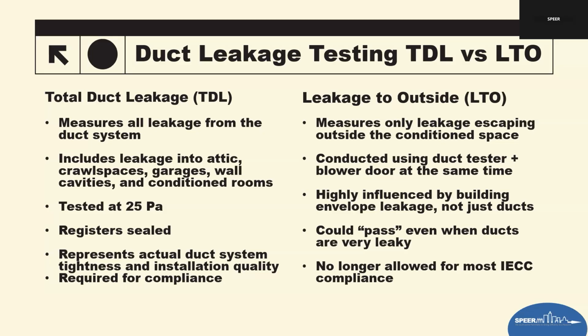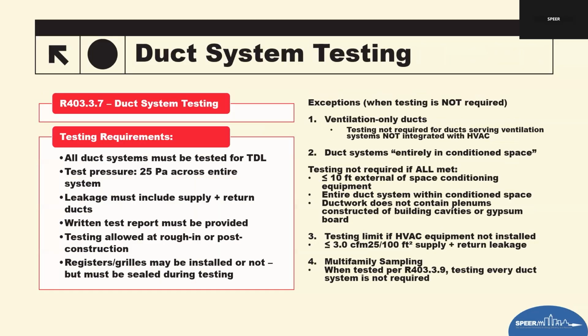Total duct leakage, TDL, aligns with the ResNet ICC 380, which is the standard that the IECC follows. It is more reflective of true workmanship, and it's the basis for setting new 2024 leakage thresholds. LTO had too much variability and too many false passes and fails. So the code moved on from that and basically goes straight to total duct leakage only as being allowed. So in the testing on this part of it, I'm just going to go through what the book says we have to do when we set up a duct test.